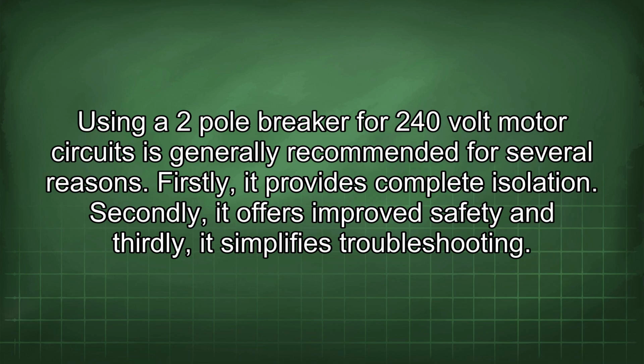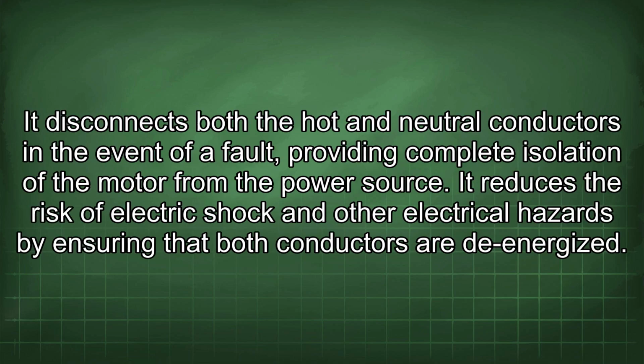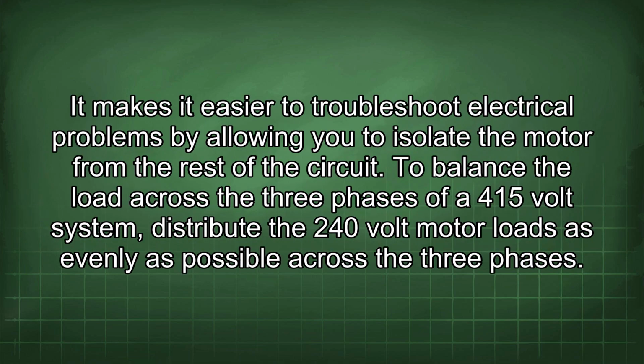Using a 2-pole breaker for 240-volt motor circuits is generally recommended for several reasons. Firstly, it provides complete isolation. Secondly, it offers improved safety, and thirdly, it simplifies troubleshooting. It disconnects both the hot and neutral conductors in the event of a fault, providing complete isolation of the motor from the power source. It reduces the risk of electric shock and other electrical hazards by ensuring that both conductors are de-energized. It makes it easier to troubleshoot electrical problems by allowing you to isolate the motor from the rest of the circuit.